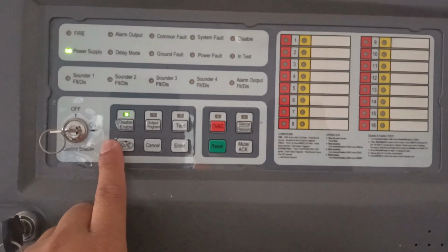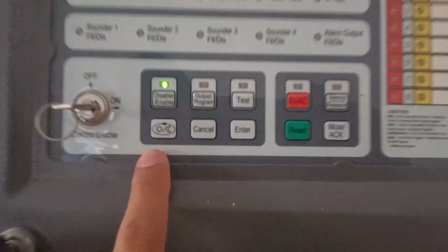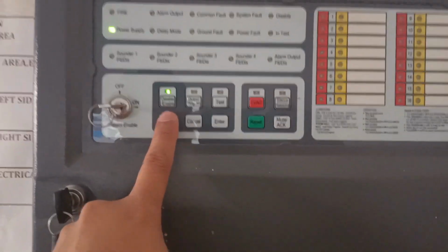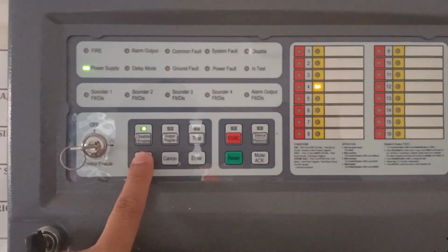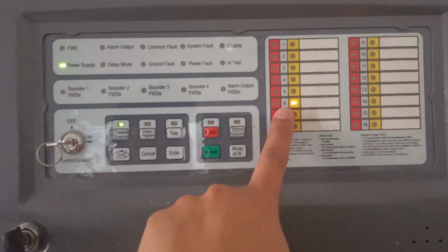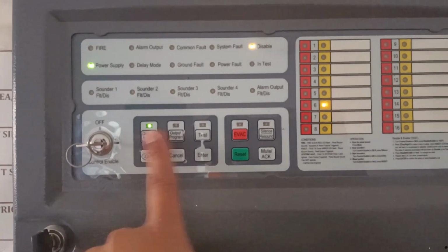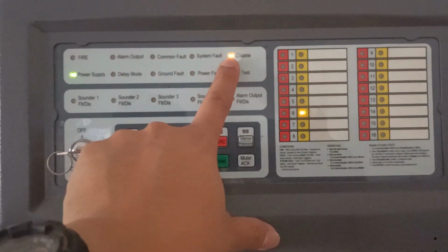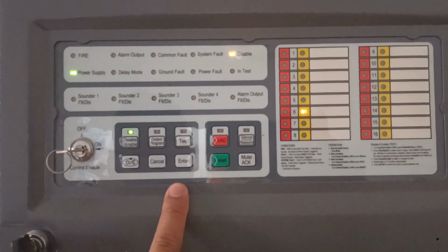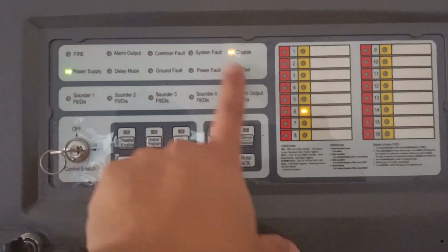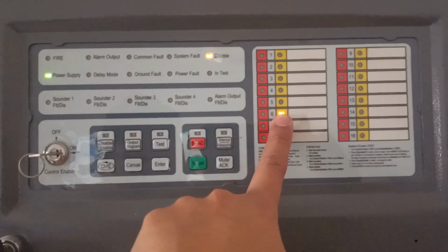So if you want to choose all zones to disable one by one, you go to disable, then choose this function. So this one going down, down, down, down, down. For example, I will disable zone 6. I press enter, so the light of disable is on. Then press enter. Then if I press cancel, it is already disabled.